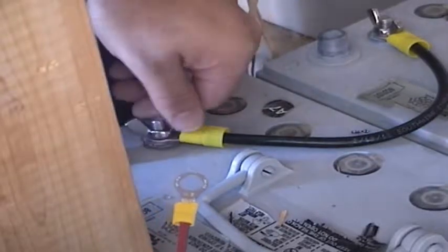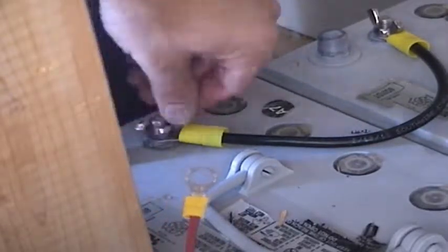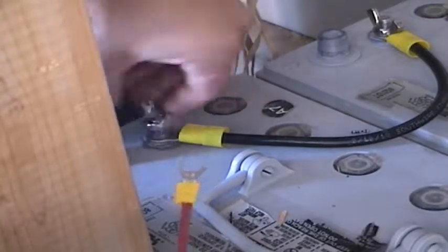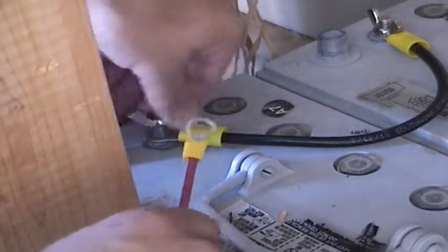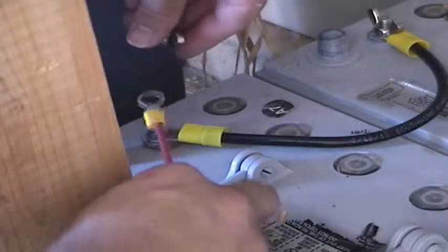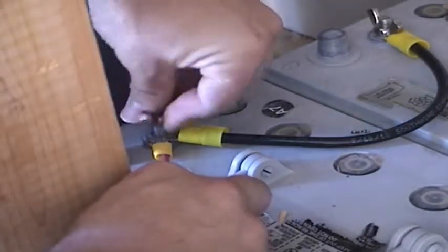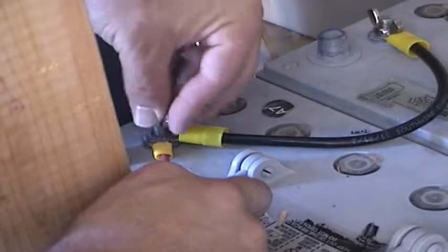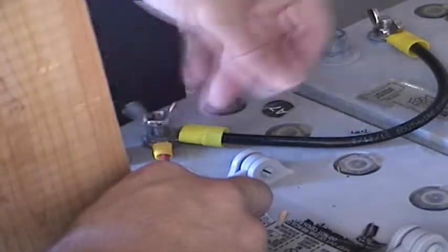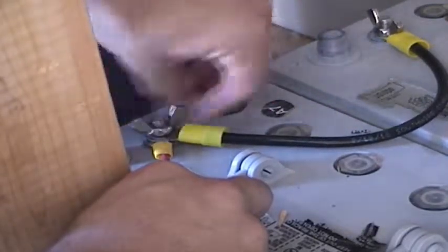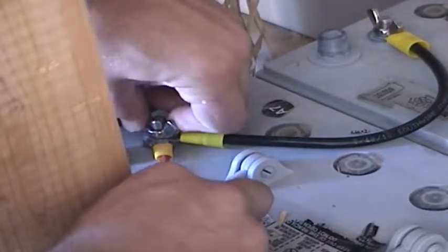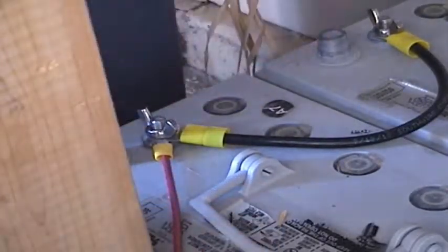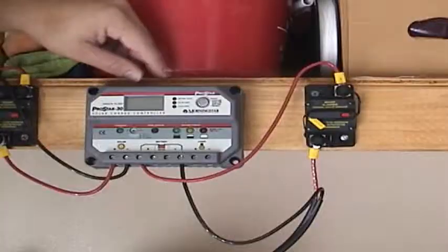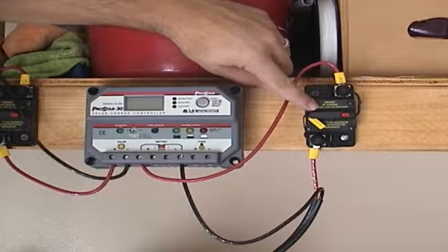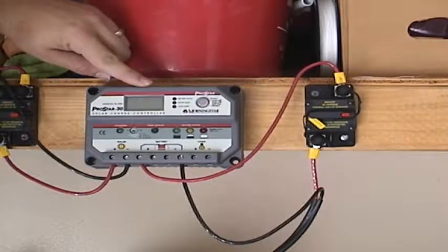Now let's go over to the plus 24 volt side of the battery bank. Remove the wing nut. Grab our red wire. Insert the ring terminal on top. Replace the wing nut. Make sure it's nice and tight. Our battery bank is now successfully wired to our solar charge controller. Now when we reset the yellow tab on circuit breaker number 2, the solar charge controller should turn on.